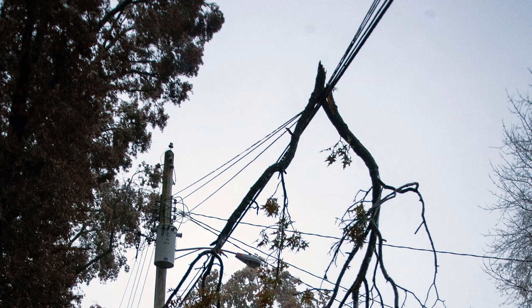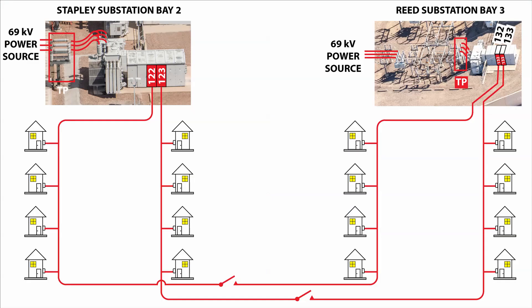Or the tree branch might be burned by the energy in the arc flash due to the fault and fall to the ground. If the fault condition is cleared, the circuit breaker will stay closed after it recloses. Most of the customers on the circuit will not even notice the brief interruption in their power, as it is just a few seconds in duration.